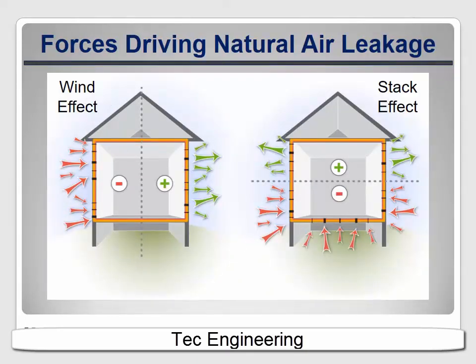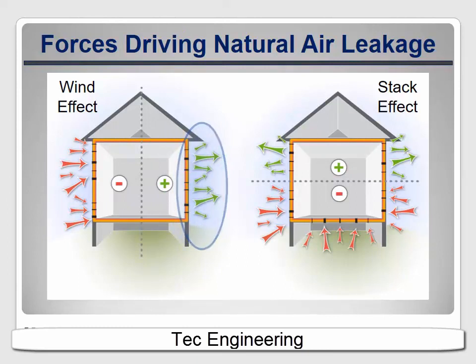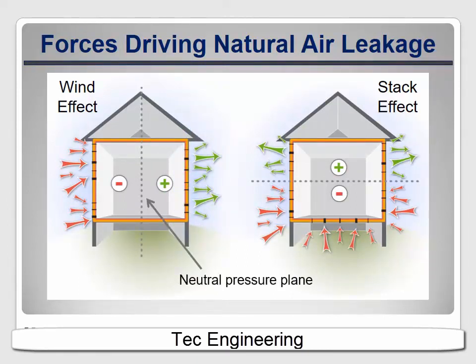When it's windy outside, that wind creates pressures around the house. On the side the wind is coming from, the pressure pushes air into the house. But on the other side, where the wind wraps around, it creates suction that pulls air out. Somewhere in the middle of the house is a vertical neutral pressure plane that divides the intake and outlet sides. The two forces work together to accelerate air leakage. But this doesn't happen all the time — it only happens when there is a significant wind outside. The buoyancy of warm air is a more significant factor, especially in cold climates.